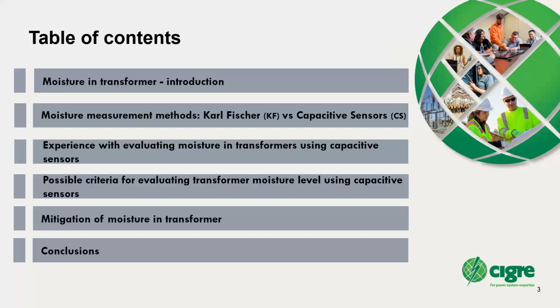I would like to talk today on several points, not everything. We have written the brochure 741, and you can read a lot of things there. I'll concentrate only on certain points. First I'll shortly talk about moisture in transformers, where it comes from. Then different measurement methods: Karl Fischer, the classical method, versus capacitive sensors. Then how to evaluate moisture in transformers using capacitive sensors, and possible criteria for evaluating transformer moisture level. This is very important because up to our work, these criteria did not exist. Then, if we have moisture in a transformer, how can we mitigate it? And of course at the end, several conclusions.